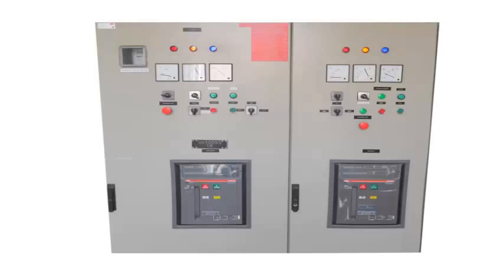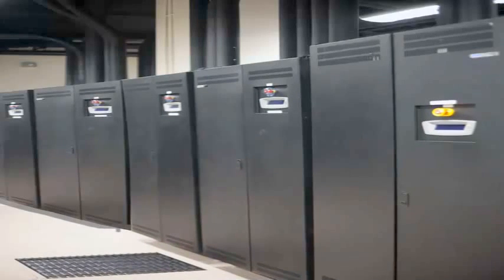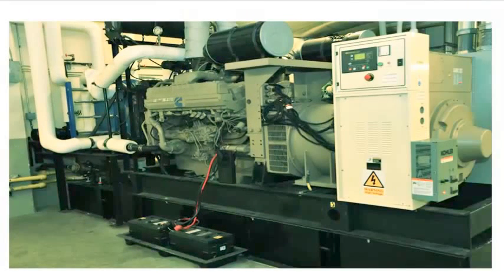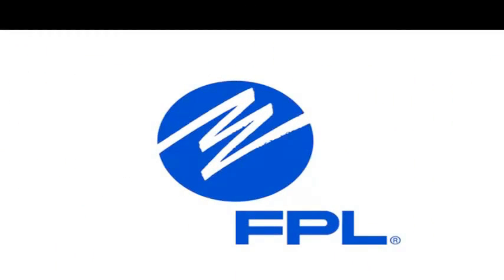Power gets to the ATS from a bank of uninterrupted power supplies, or UPS systems, that draw power from two different sources. One draws from an emergency generator available to kick on immediately in the event of a complete power failure in the area, and the other is connected to FP&L, with our data center actually in the middle of two different grids, so there are two grids that can potentially power it.